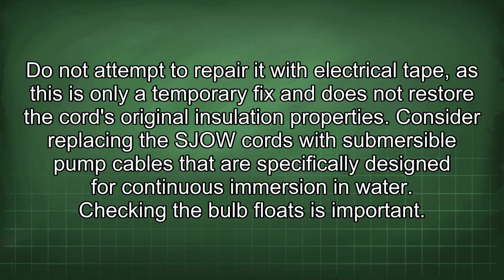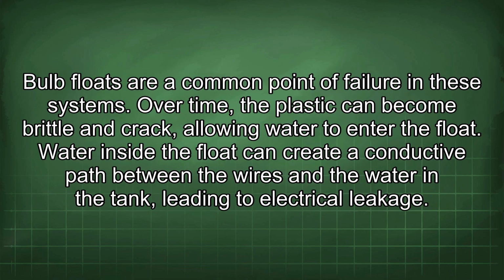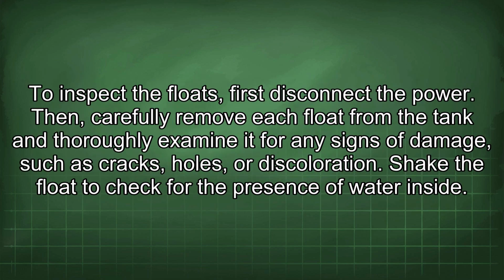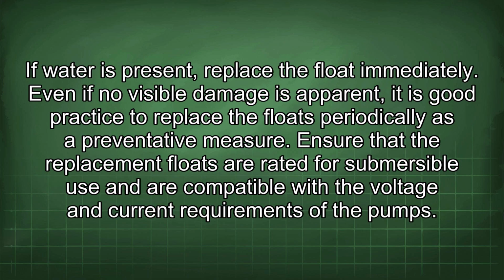Consider replacing the SJOW cords with submersible pump cables that are specifically designed for continuous immersion in water. Checking the bulb floats is important. Bulb floats are a common point of failure in these systems. Over time, the plastic can become brittle and crack, allowing water to enter the float. Water inside the float can create a conductive path between the wires and the water in the tank, leading to electrical leakage. To inspect the floats, first disconnect the power. Then carefully remove each float from the tank and thoroughly examine for any signs of damage, such as cracks, holes, or discoloration. Shake the float to check for the presence of water inside. If water is present, replace the float immediately.